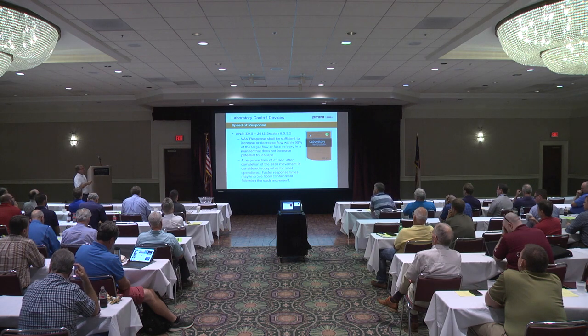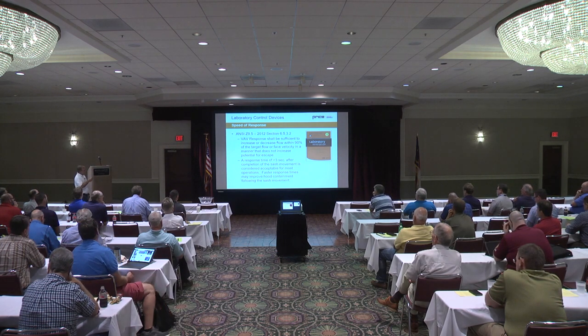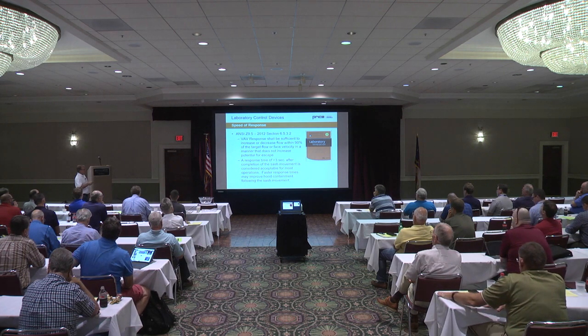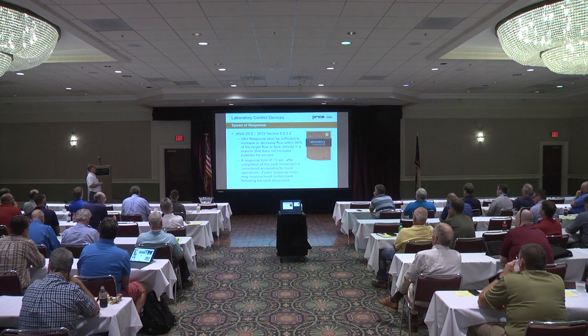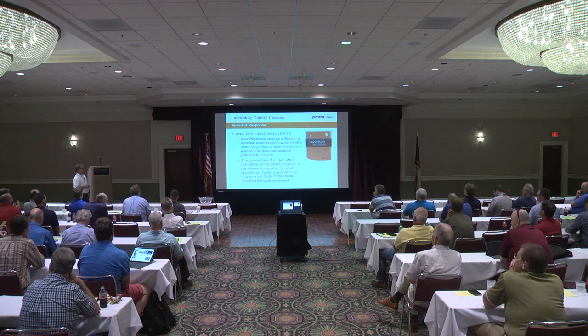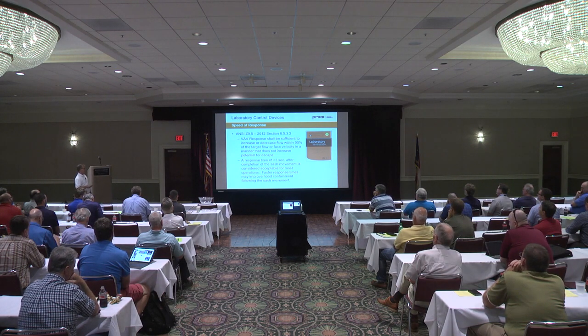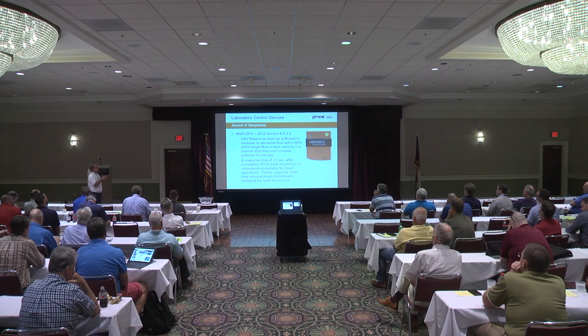So speed of response in laboratory ventilation: VAV response should be sufficient to increase or decrease the flow within 90% of the target flow or face velocity in a manner that does not increase potential for escape. Response time of less than 3 seconds after completion of the sash movement is considered acceptable for most applications. Faster response times may improve hood containment. So the ANSI document states 90% of flow and within 3 seconds after movement of the sash.